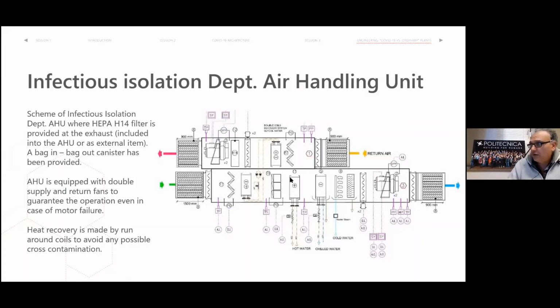The heat recovery is made by a run-around coil like this. In an infectious isolation department, in these high care departments, you cannot have, let's say, cross-flow heat recovery or rotary heat recovery, because there could be a certain bypass between supply and return. And this is absolutely not allowed in this case. And so we use heat recovery made by two coils. So there is no mixing, it is absolutely impossible to have mixing and to have cross-contamination.